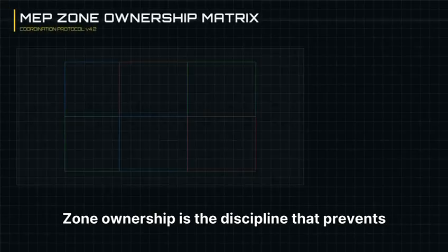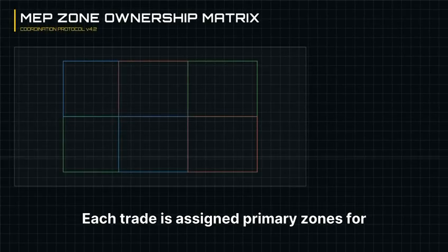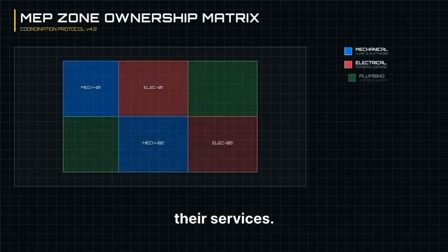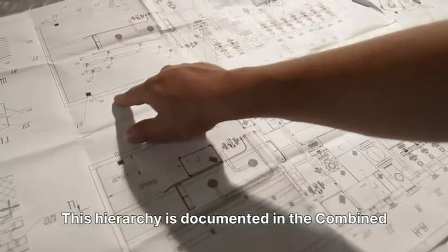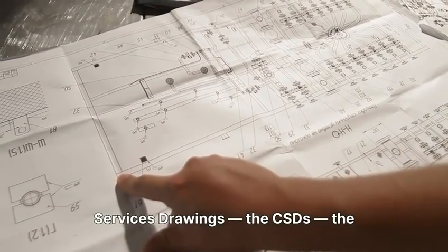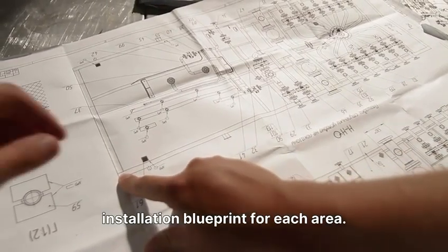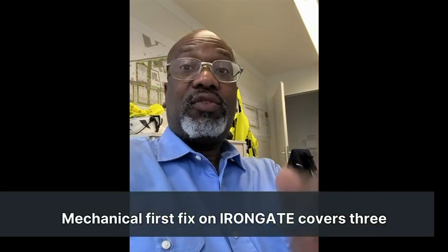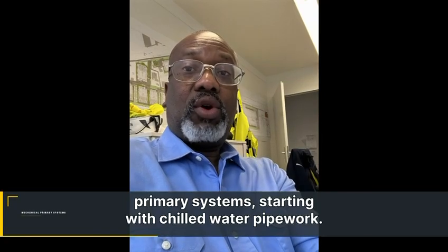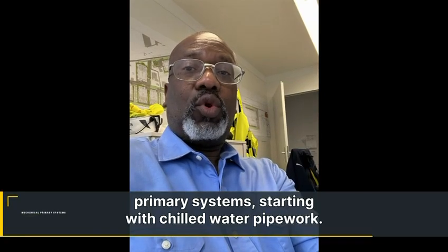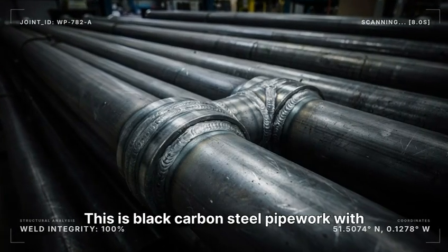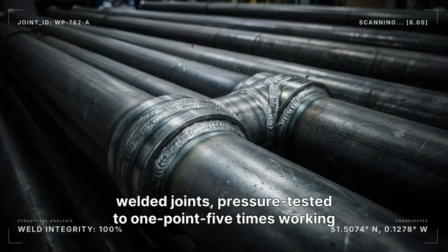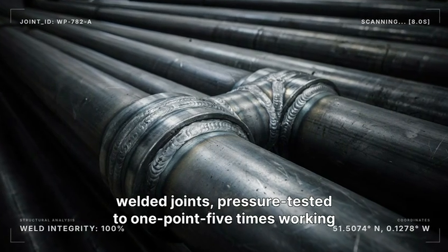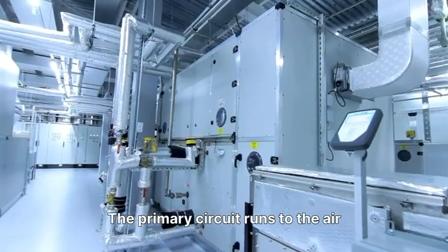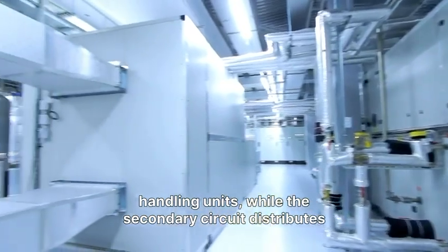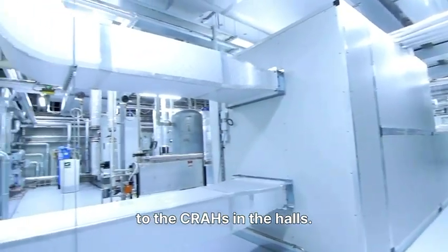Zone ownership is the discipline that prevents clash recurrence. Each trade is assigned primary zones for their services. This hierarchy is documented in the Combined Services Drawings, the CSDs, the installation blueprint for each area. Mechanical first fix on IRONGATE covers 3 primary systems, starting with chilled water pipework. This is black carbon steel pipework with welded joints, pressure tested to 1.5 times working pressure. The primary circuit runs to the air handling units, while the secondary circuit distributes to the CRAHs in the halls.